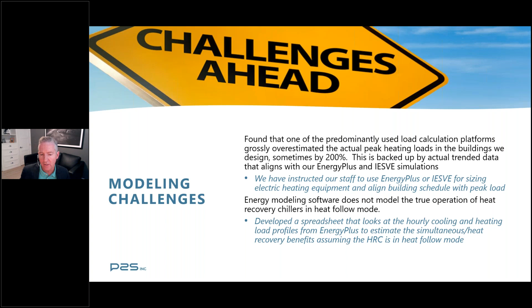That platform is soon to be replaced next year with a different platform by the manufacturer that provides it. Also, on energy modeling software, many people are looking at heat pump technology when there's simultaneous heating and cooling, might be domestic hot water and space heating, when they can actually use the chilled water that's coming off of that. And there's currently not any platform out there on the energy modeling side that can actually model heat recovery chillers in a heat follow mode. They model them in a cooling follow mode, and that's not the way you would operate it if you're providing your primary heating and getting the cooling as a secondary effect. Next slide, please.